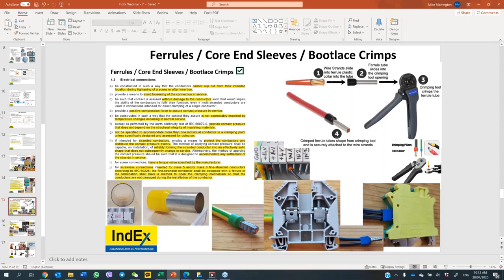In the case of double wire inside of a bootlace ferrule and single terminal, does this typical installation affect the temperature rise calculations for the number of terminals? Well, yeah, you have to tell the manufacturer how many wires you plan to use. So if you were asking Stahl or Eaton, this would be part of the information you would give them that they would then use for their temperature calculations.